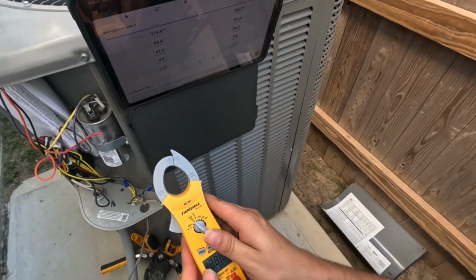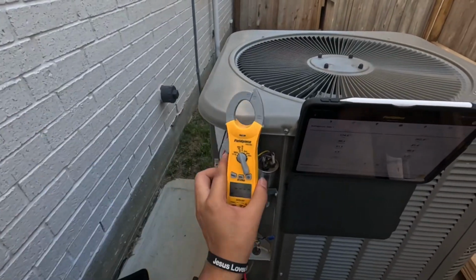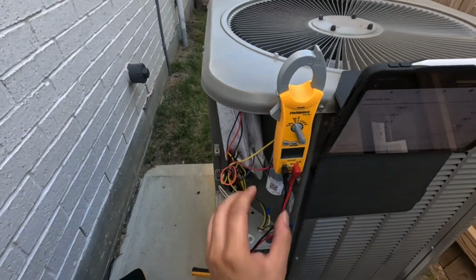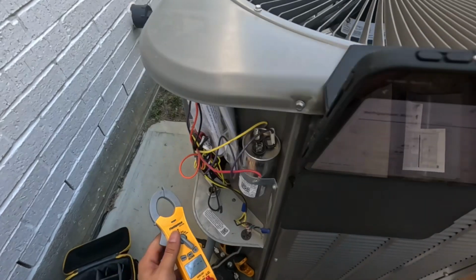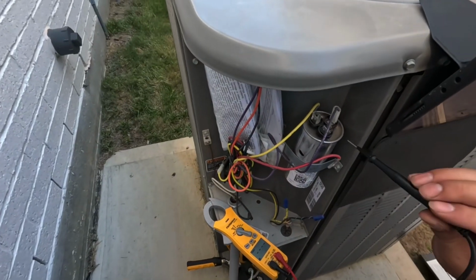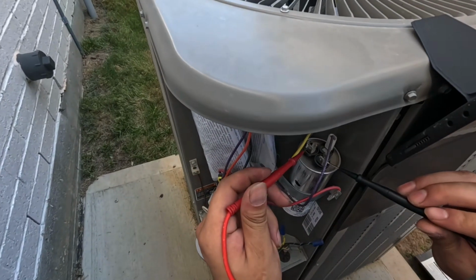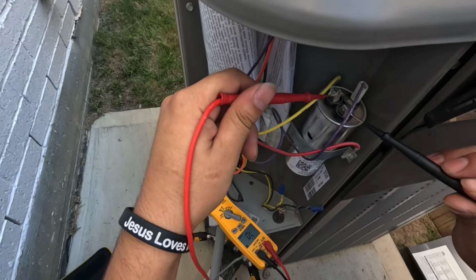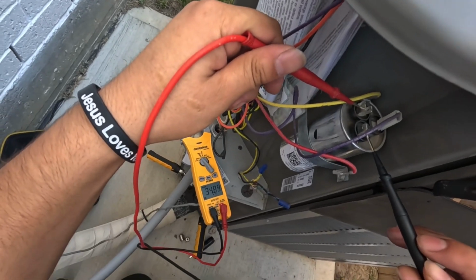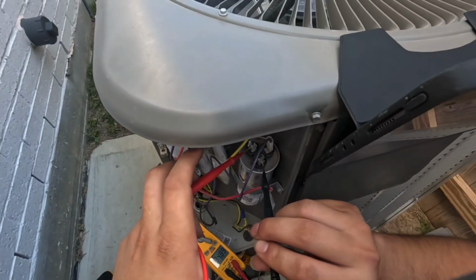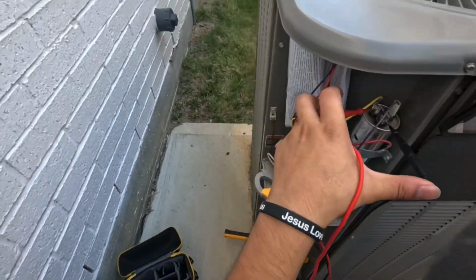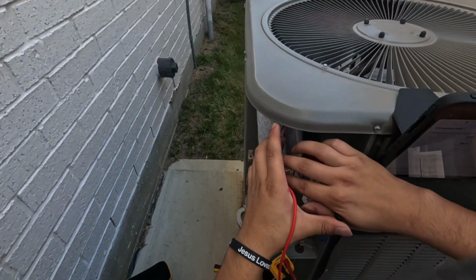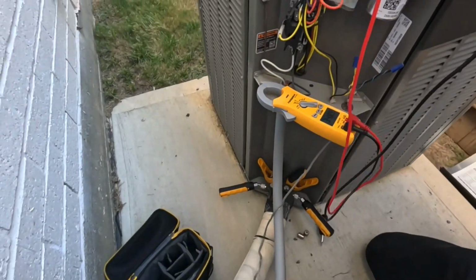So we're gonna put it on microfarad right here. And this is supposed to be a 35 because it's a compressor. It's reading 34, that's good. So it can't be 5% below the tolerance because then it's gonna go in bad already. This is pretty good.